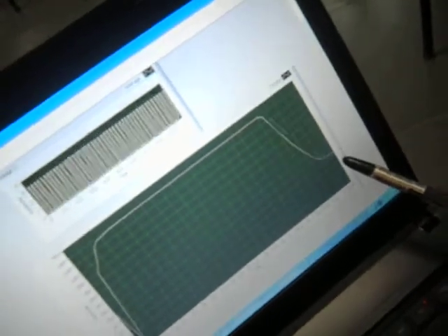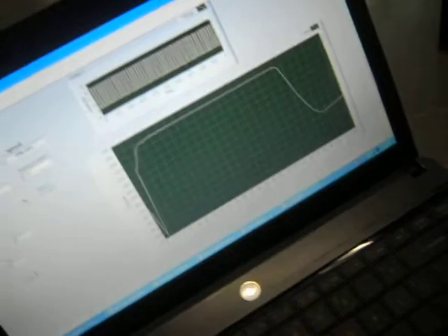We enter, and you can see the motor is retarding. You can actually hear the sound of the retarding motor, and yes, it comes to 500 RPM, and thereafter, some time later, you can see the stabilizing of the motor at 500 RPM. This is how it is done.